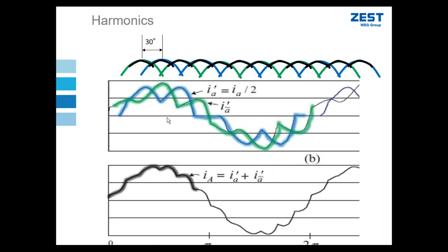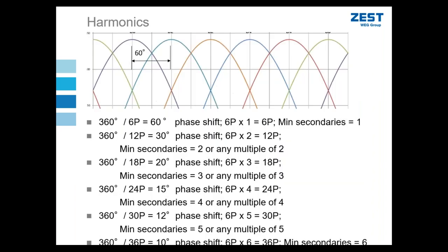So this showed a 12 pulse system. A 12 pulse system has 12 voltage pulses in the DC link voltage ripple and 30 degree angle, peak to peak. But we can introduce additional rectifiers. We can continue adding six pulse rectifiers either in series or in parallel. And we can adjust their phase angles to increase the number of pulses. So if we take the simple case, 360 degree single cycle divided by six pulses gives me my 60 degree angle peak to peak that we've already discussed.